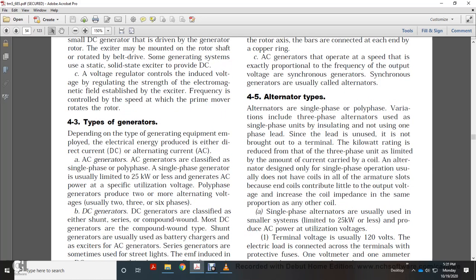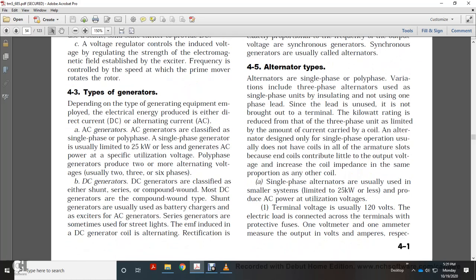Alright, alternator types. Alternators include single phase and polyphase variations, including the three phase alternator. With the single phase unit, one phase lead is not brought out to a terminal, so the kilowatt rating is reduced to that of the three phase, limited by the amount of current carried by the coil. An alternator designed only for single phase operation usually does not have coils in all the armature slots. End coils can contribute little or no output voltage increase, with coil impedance in the same proportion as any of the other coils.